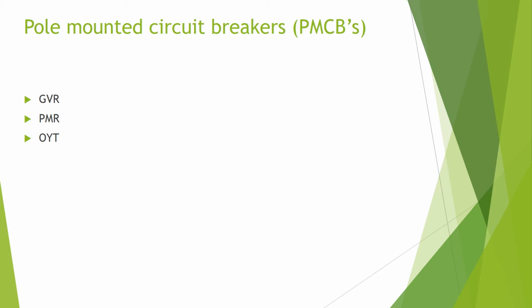They usually will reclose after a trip caused by a fault on the line a number of times in an attempt to clear or sectionalize off a fault. They are all also able to be hand operated using insulated operating rods. All PMCBs are rated to at least 400 amp.